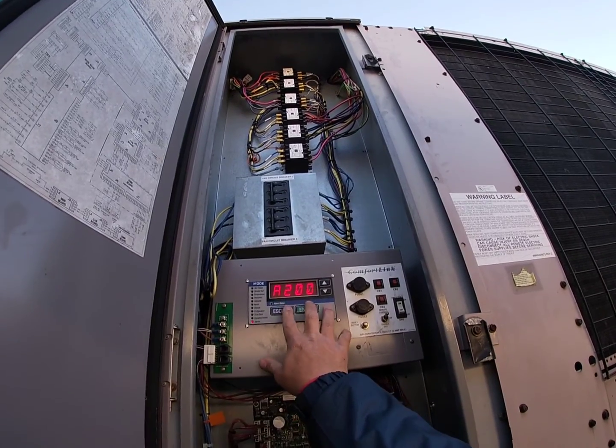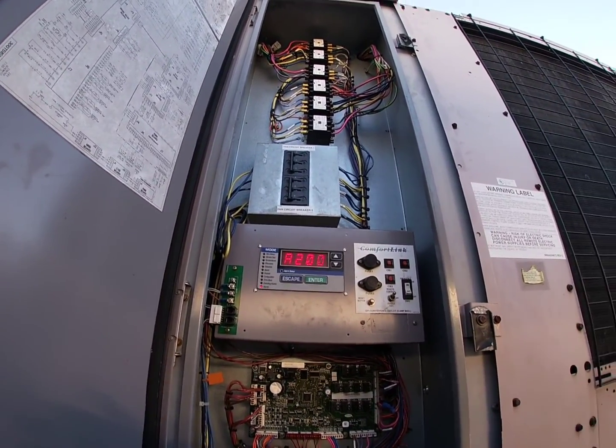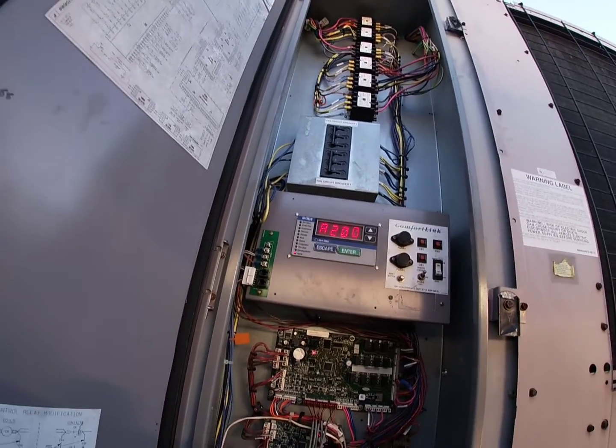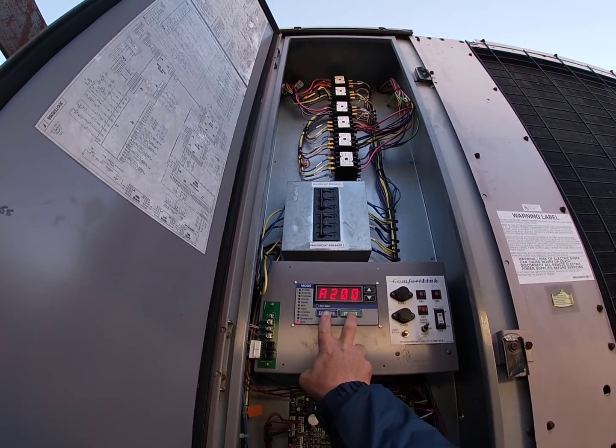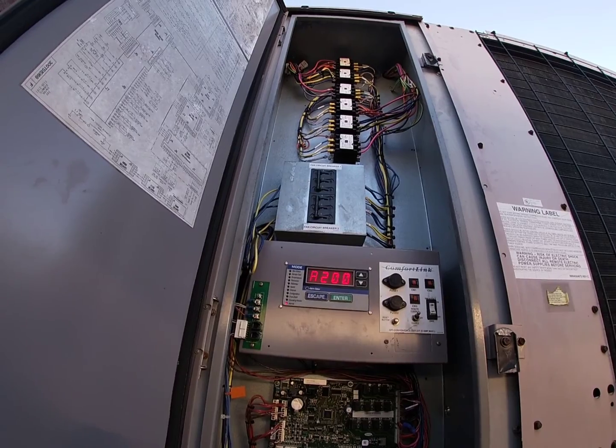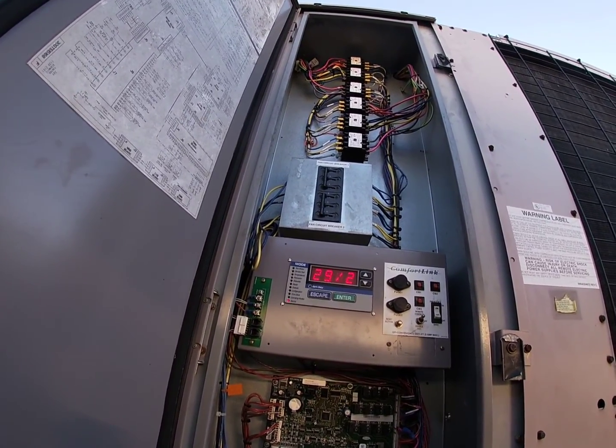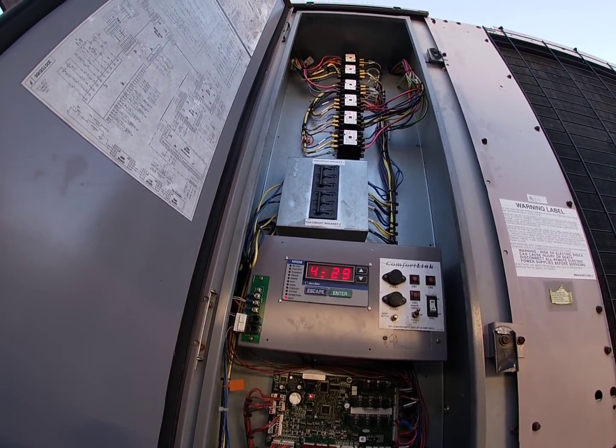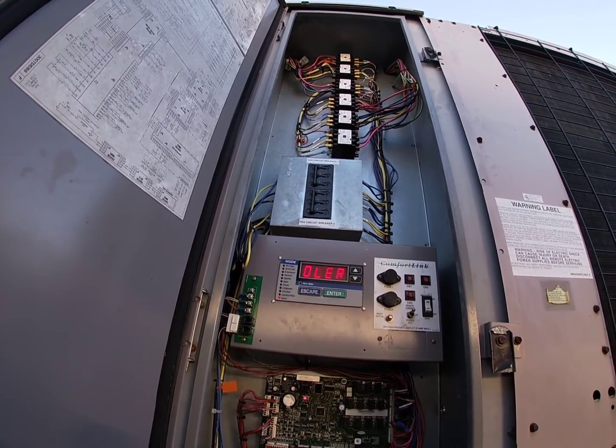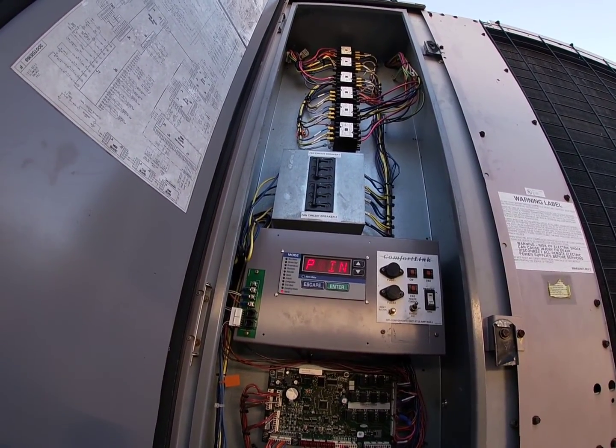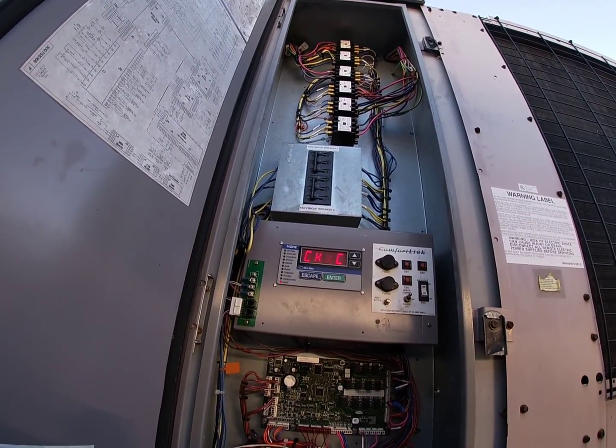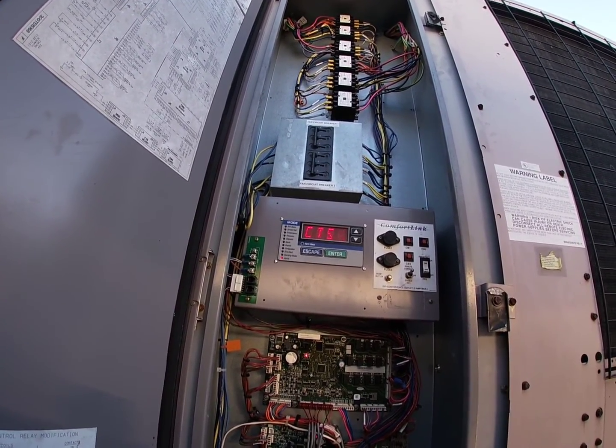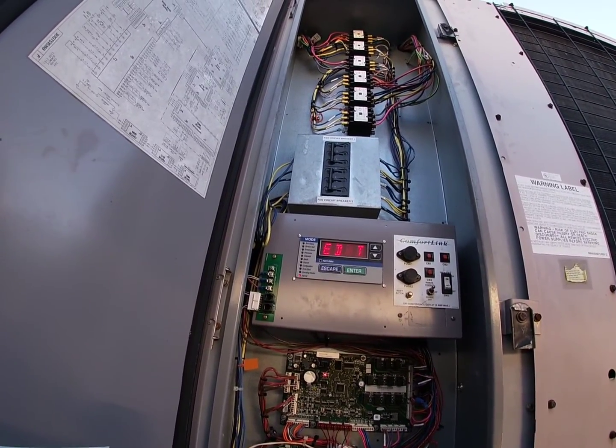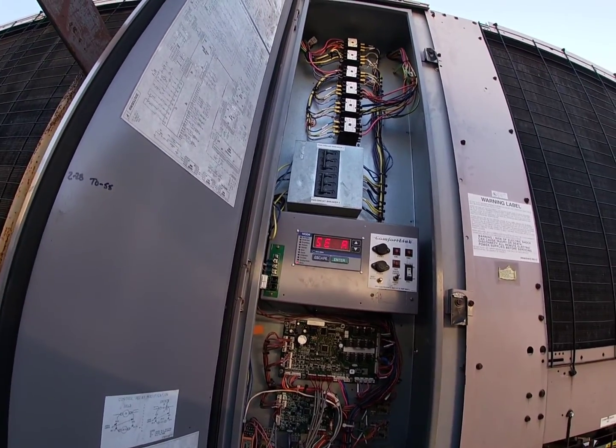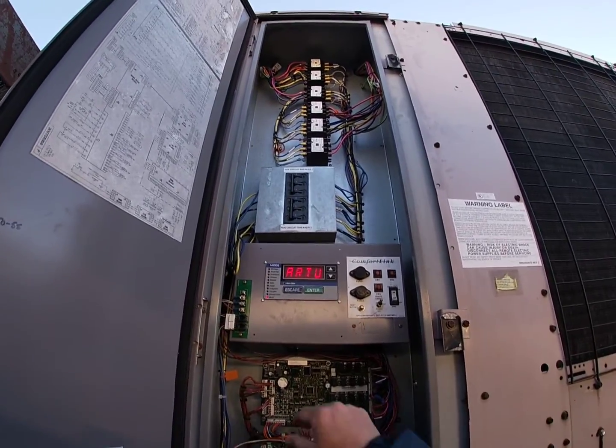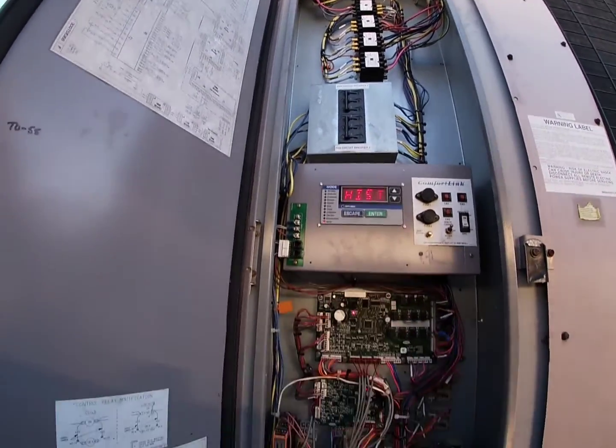A200. In case you guys get this and you want to see what alarm that is without having to go in the book, you're gonna hit enter and escape at the same time. Let go, and it gives you time, date, cooler pump interlock contacts failure or fail to close. So that way you kind of know what's going on here. So we got an issue with the pump.